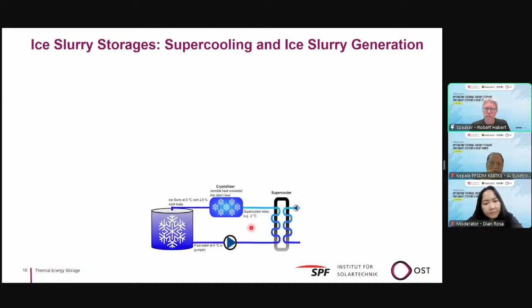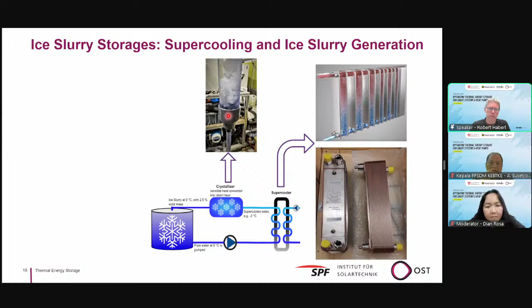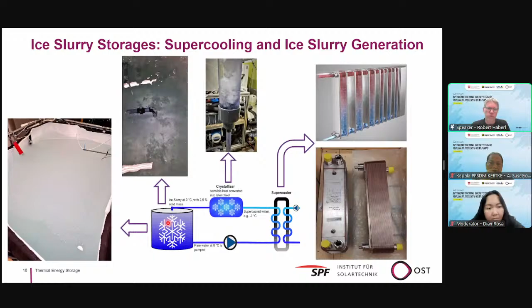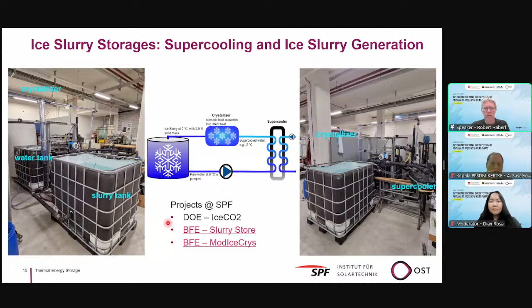So the ice slurry storages use a heat exchanger that has to be coated with an icephobic coating. With that heat exchanger, you supercool the water and you bring it to a crystallizer that starts the nucleation of ice cores. And then you can put this ice in a tank and use that ice later for different cooling applications. We tested that in our lab, and we have several projects. Maybe when you want to have a look at those projects, you can follow those links, where different ice slurry projects are documented, which is, I think, an interesting technology for Indonesia because of the cooling demand.